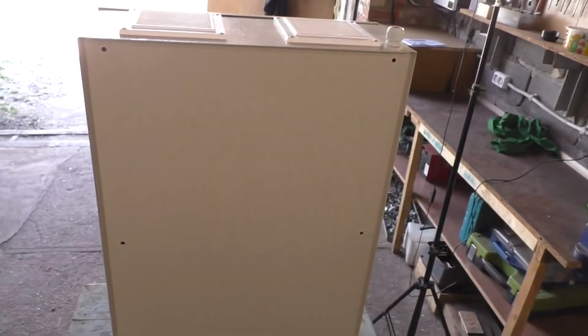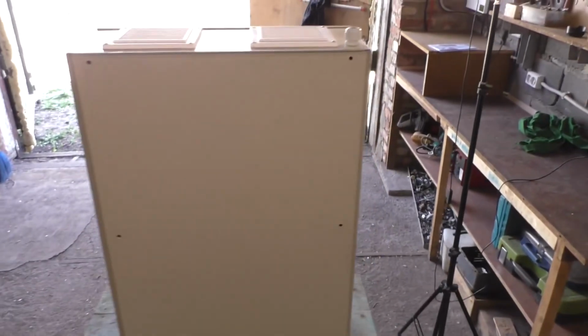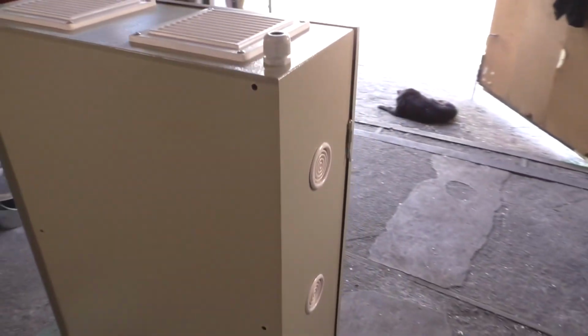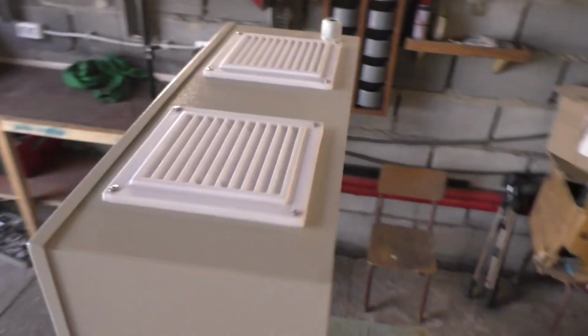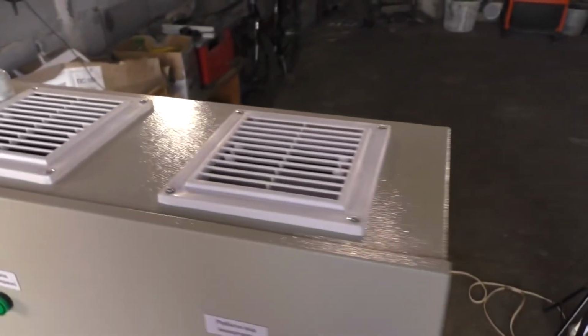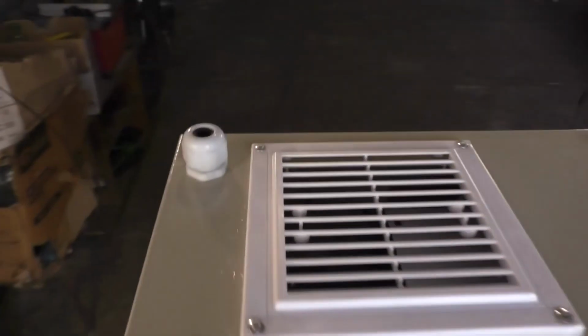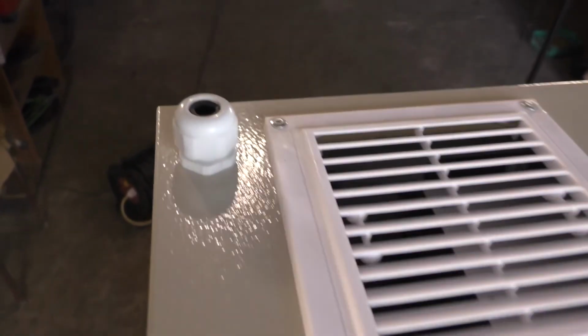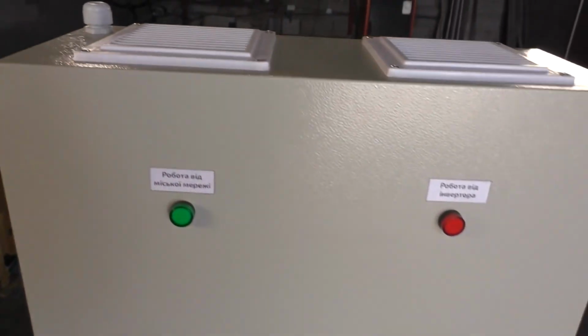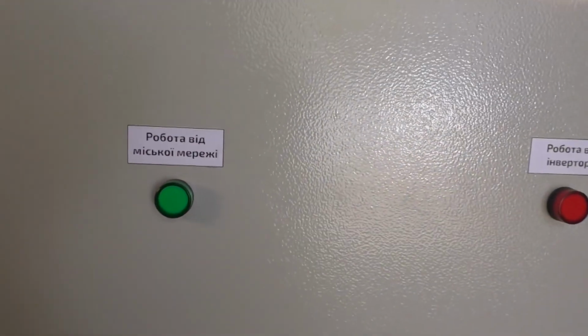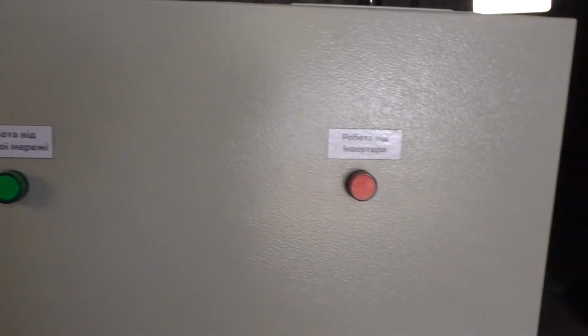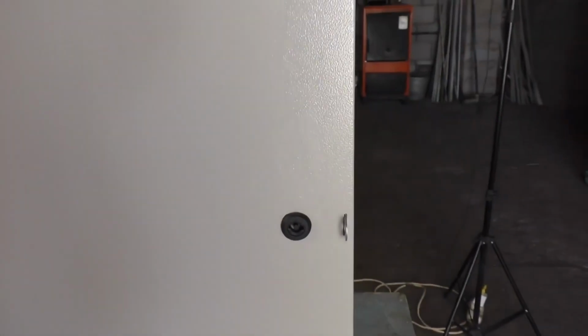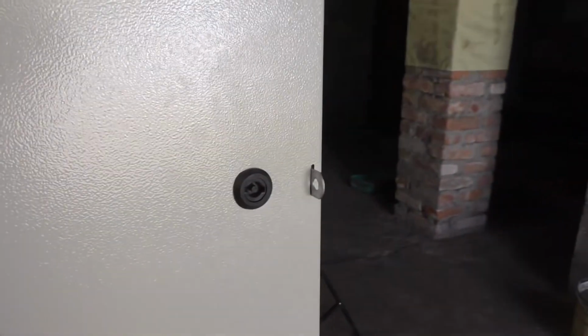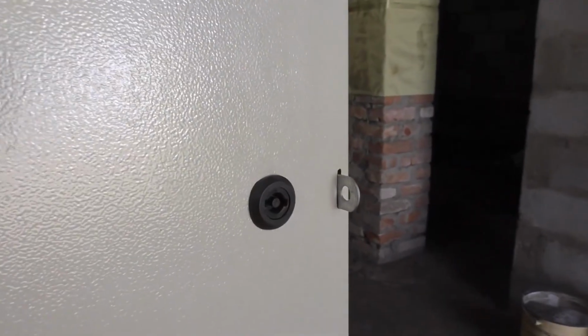There are 6 holes on the back of the panel so you can mount it on the wall. There are ventilation grills installed on the sides as well as on the top and bottom for equipment ventilation. In the upper left corner, there is a cable entry point to connect this device to your apartment. On the front panel, there are 2 indicator lights that show which input is currently in use. The green light indicates utility power and the red light indicates the inverter. The panel is locked with a special key and there is also a hasp for a padlock.